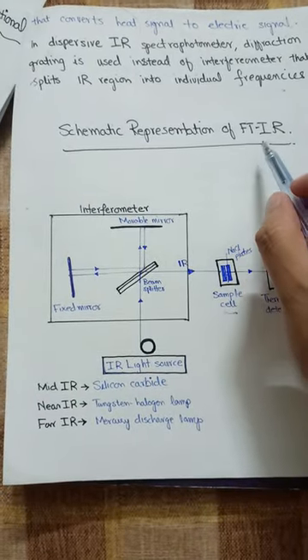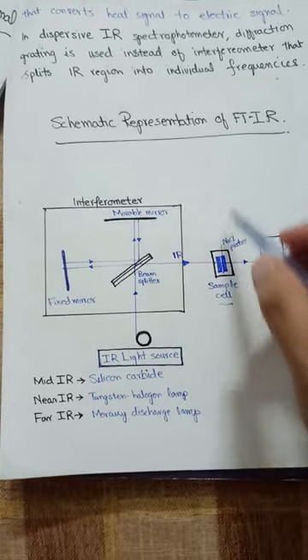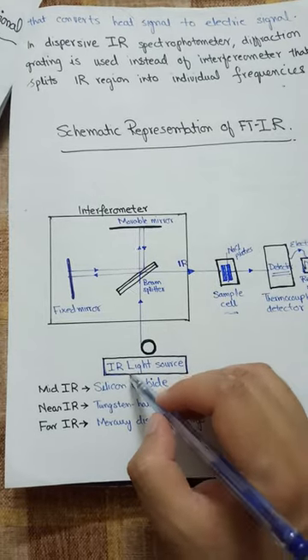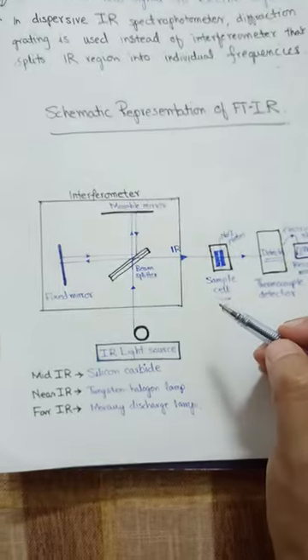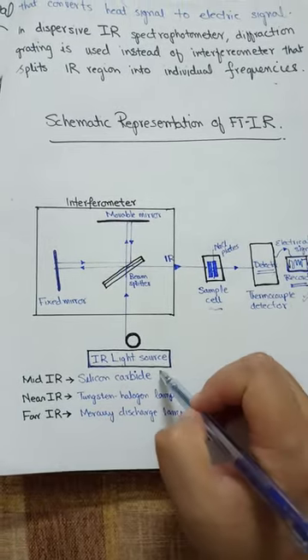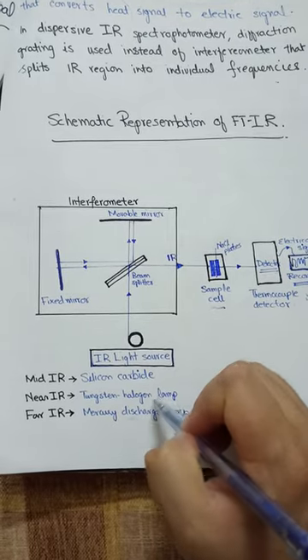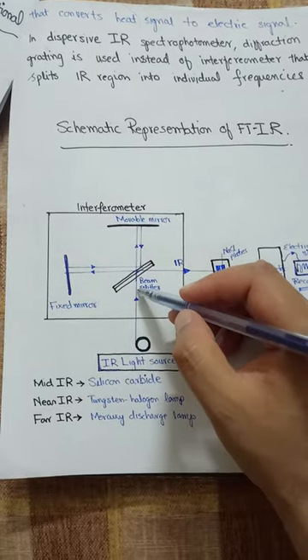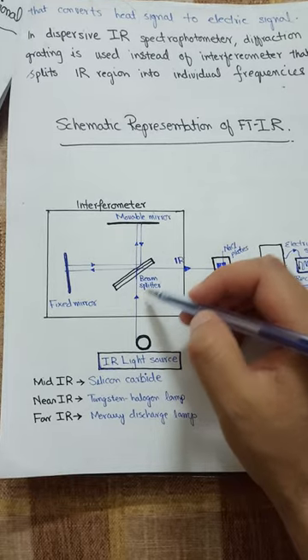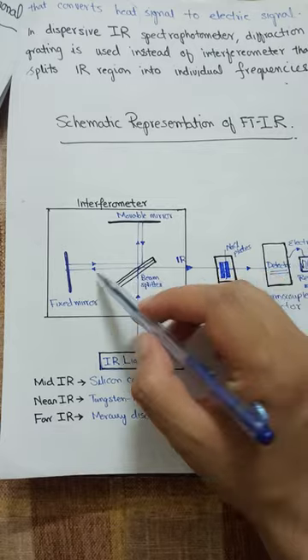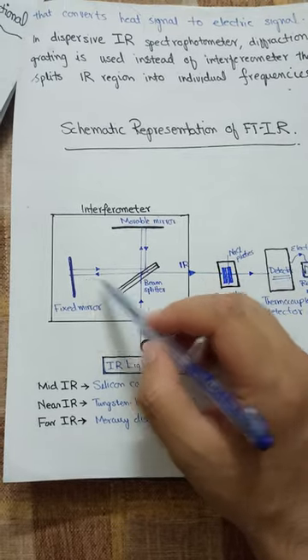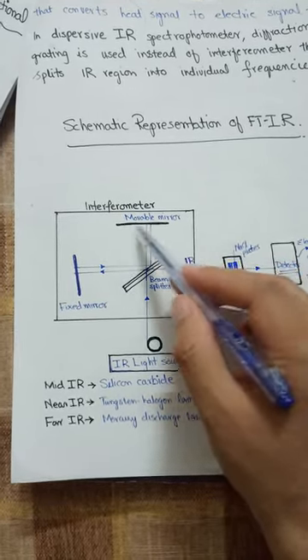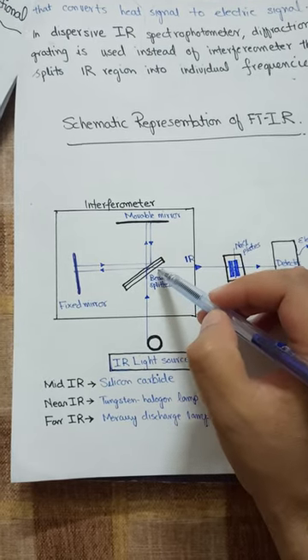Here we have a schematic representation of the Fourier transform infrared spectrophotometer. First is the light source in the infrared region — silicon carbide for mid-IR, tungsten halogen lamp for near-IR, and mercury discharge lamp for far-IR. These IR radiations pass through the interferometer, where the beam splitter splits the beam into two equal paths: one is reflected onto the fixed mirror.